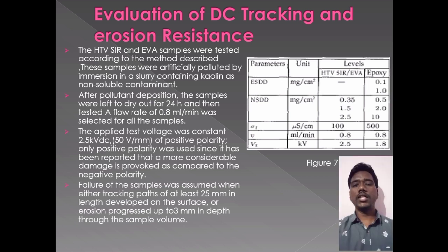In method 2, samples were artificially polluted by immersion in a slurry containing NaCl as a soluble material. The non-soluble fraction was provided by a proper amount of kaolin. Two levels of test voltage and equivalent salt deposit density were adopted. Three different values of NSDD were selected. As in the test of HTV, SIR and EVA samples, the applied voltage was of positive polarity and maintained constant along the entire test duration. The maximum duration of the test was defined as 8 hours.